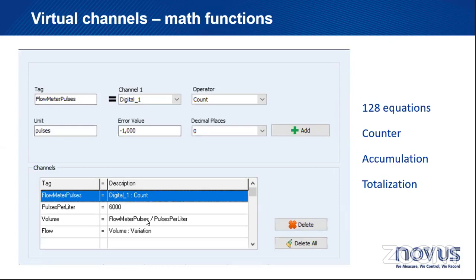How do I do that? Well, I have to do a variation. What does the variation do? I'll select the operator variation, and I calculate the variation on volume. This is basically a derivative calculation. When you select variation, there's a time configuration. So I have selected, for example, 60 seconds. So every 60 seconds, I will calculate my variation so I can find out my flow in liters per minute.